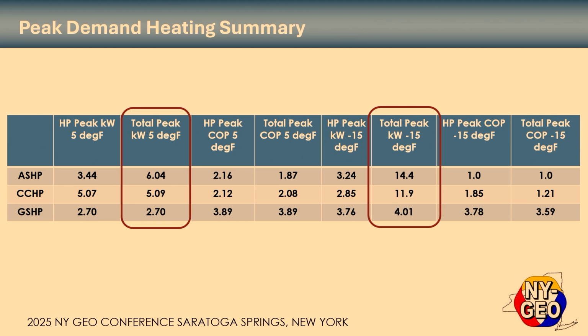Yeah. So for cooling, the numbers probably are at least close, because that assumes that you're running pretty well full out. And I think that, on a hot day, is probably what you would have in a commercial building. So you'd have to just get the right equipment in there, but essentially variable speed versus loop temperatures versus outdoor air temperatures, that ratio is probably not that much different. Of course, you could have a cooling tower, you could have other stuff with the water source unit. But as I said, this is based upon actually probably a high 70s loop temperature, which would be typical for Albany here in the summer.